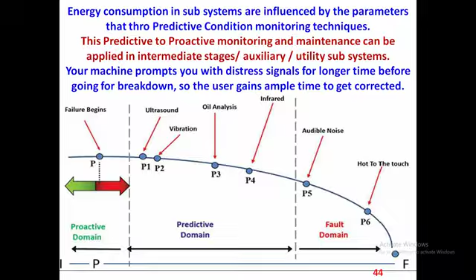Then comes the infrared. If you see, the infrared imaging is almost at the tail end of the failure. Then comes the audible noise from a given motor or machine, then the machine becomes very hot to touch and fails already. So you have a scope towards ultrasound, vibration analysis, oil analysis from the mechanical department, infrared analysis from both electrical and mechanical departments. You can do wonders in the industry with non-invasive, portable instruments for predictive maintenance. These were costing more than 10 lakhs before, and have come down to a few lakhs now. Each and every college is supposed to have these types of portable audit tools to assess the machine's health and the process health as such.